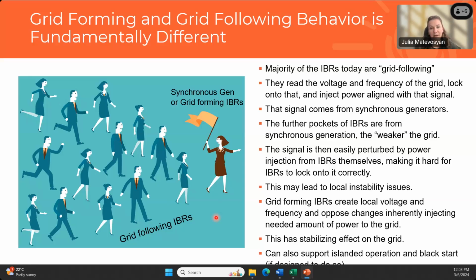And in my previous slide, I had this weak grid notion when you have a lot of IBRs. What it means then is that signal that IBRs need to lock onto is easily perturbed by power injections from the IBRs themselves. And so it's making it hard for IBRs to lock onto it correctly. So basically IBRs are kind of distorting the signal for themselves, and it becomes harder for them to inject power which is aligned with the grid signal. And this may lead to local instability issues.